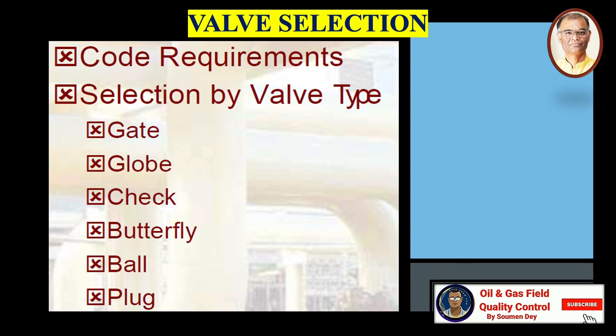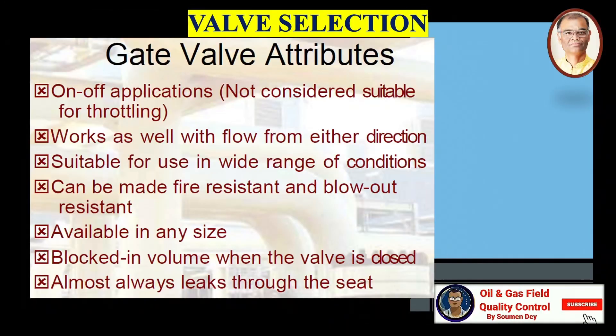Selection by valve type: we will select the gate valve for on and off applications. It is not considered suitable for throttling, works well with flow from either direction, suitable for use in a wide range of conditions, can be made fire resistant and blowout resistant, available in any size. There is blocked-in volume when the valve is closed, and it almost always leaks through the seat.